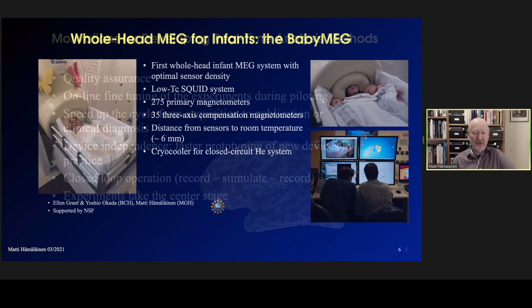We have built recently 3 different devices, each of which requires specialized real-time software which is not available otherwise. First of them is the so-called baby MEG, which is the whole head MEG device for infants at Boston Children's Hospital. This has a dense array of SQUID sensors close to the baby's head, and also 35 triplets of compensation sensors for disturbances. And as you can see, babies are quite happy being recorded in these devices, and it's not scary at all, at least after some accommodation.